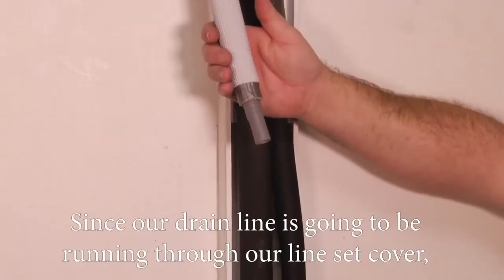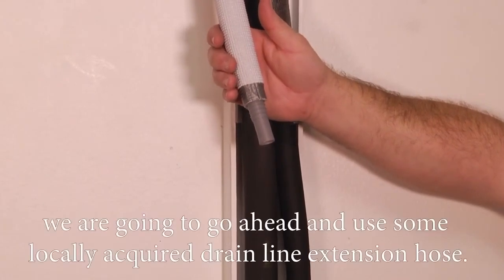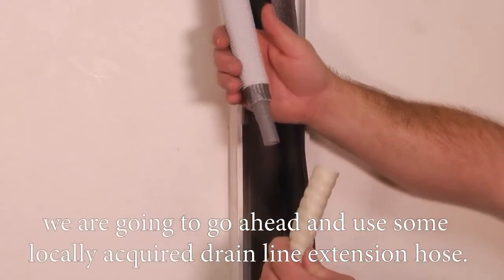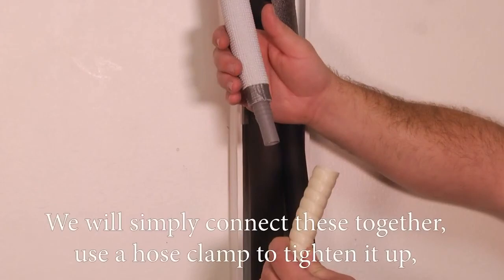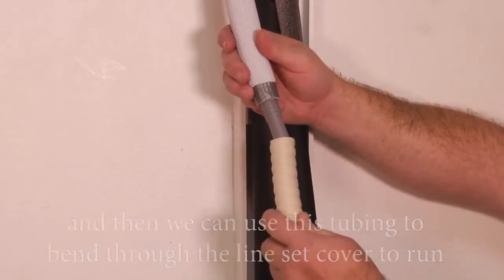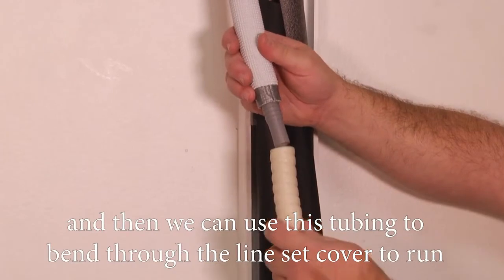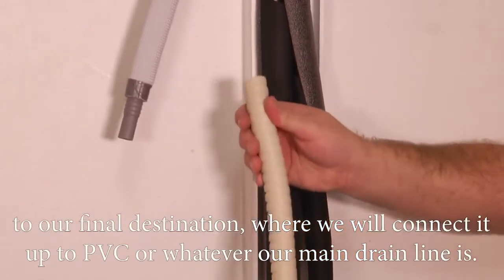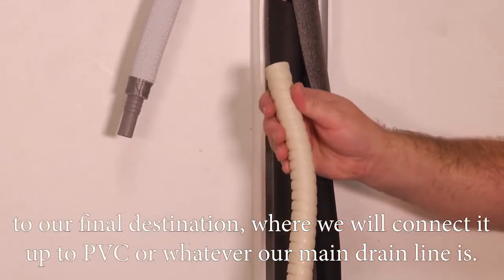Since our drain line is going to be running through our line set cover, we're going to go ahead and use some locally acquired drain line extension hose. We'll simply connect these together, use a hose clamp to tighten it up, and then we can use this tubing to bend through the line set cover to run to our final destination, where we'll connect it up to PVC or whatever our main drain line is.